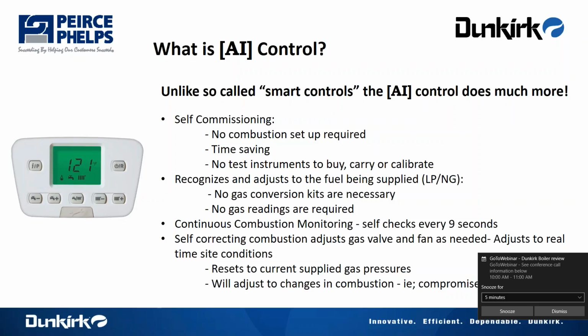The AI control, we throw AI around a lot. Artificial intelligence, it's on everything. This is a little more than that. Rather than communicating simple system degrees and temperatures and what ambient temperature is the boiler seeing or what set point it's going for, the boiler is actually a self-commissioning unit. You don't need instruments to set this up. You don't have to have calibrated instruments. It's going to do it on its own. That's going to save you a lot of time on the job. As you're cleaning up your tools, the boiler is running through its self-commissioning.